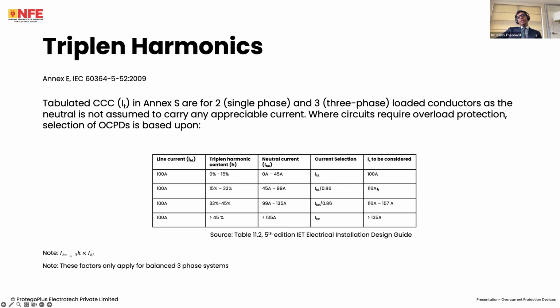Now you have to consider a 100 amp current in the line conductor. With 45% triplen harmonic distortion, 135 amps will flow in the neutral. Now we can no longer select the current on the basis of the line conductor current, because the cable has to be selected on the basis of the neutral conductor. So we do 135 divided by 0.86, we get up to 157 amps. So the current Iz value that we are looking at is 157.